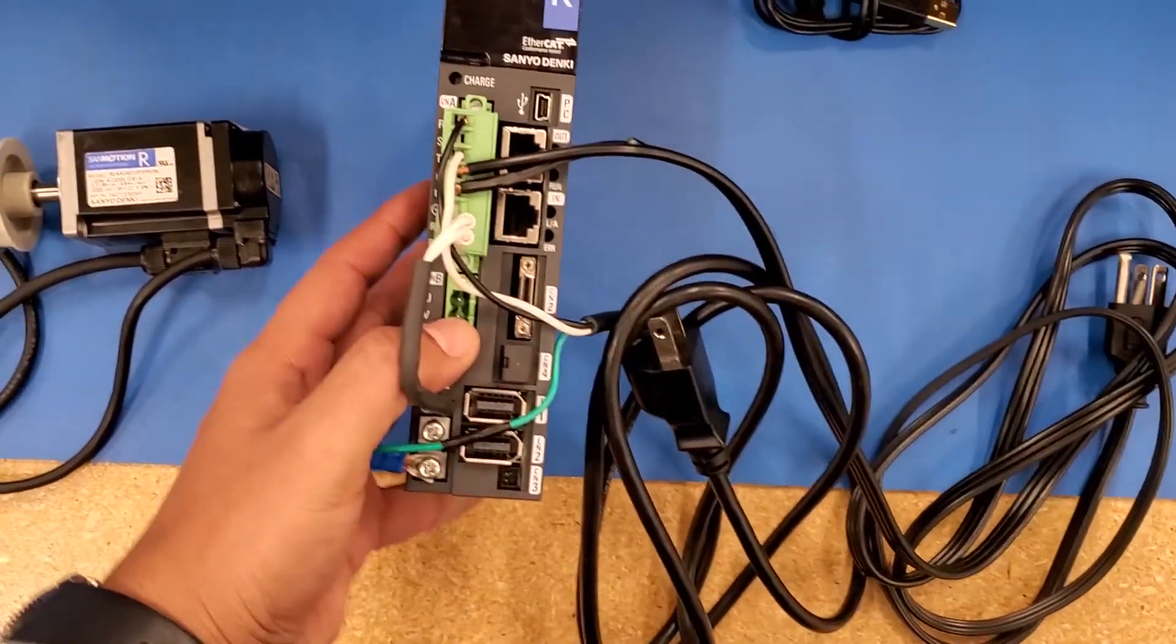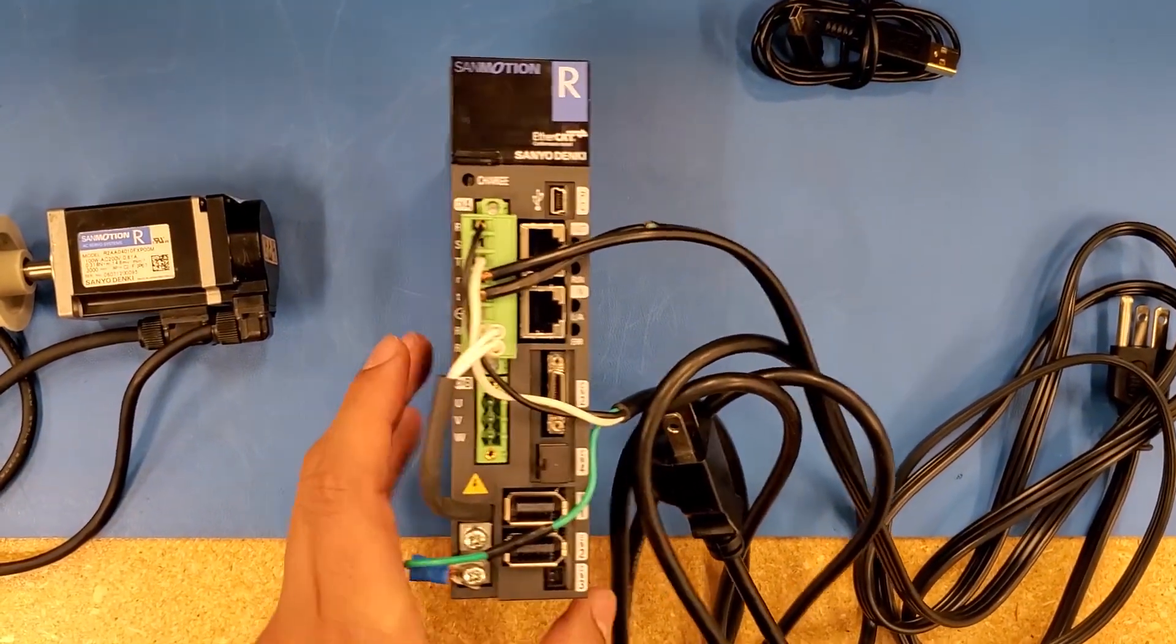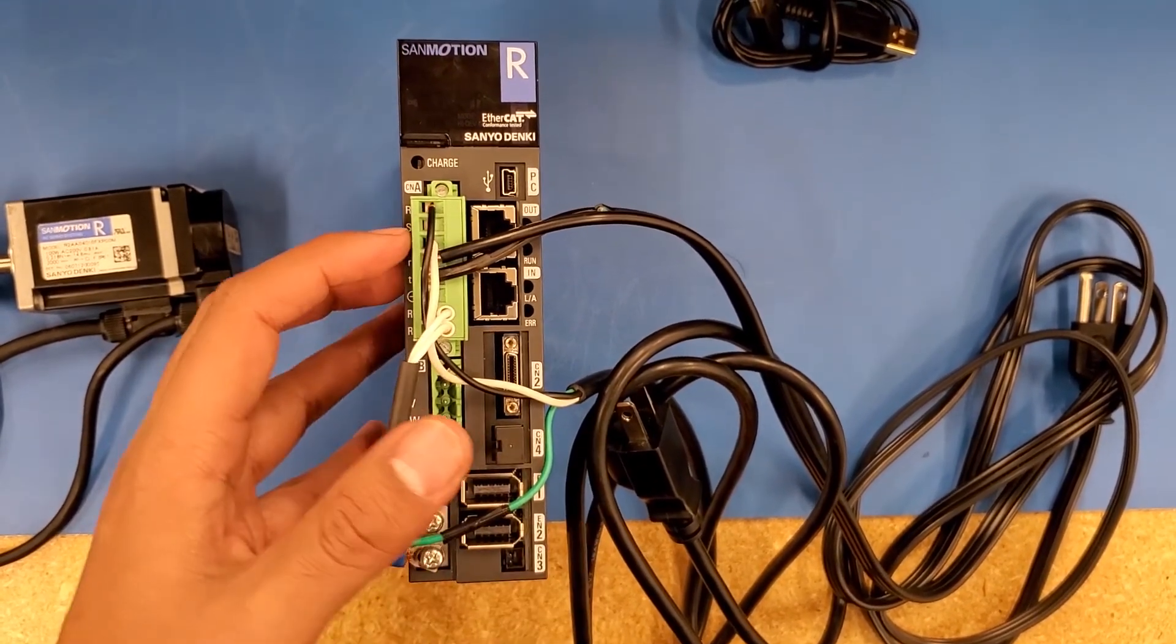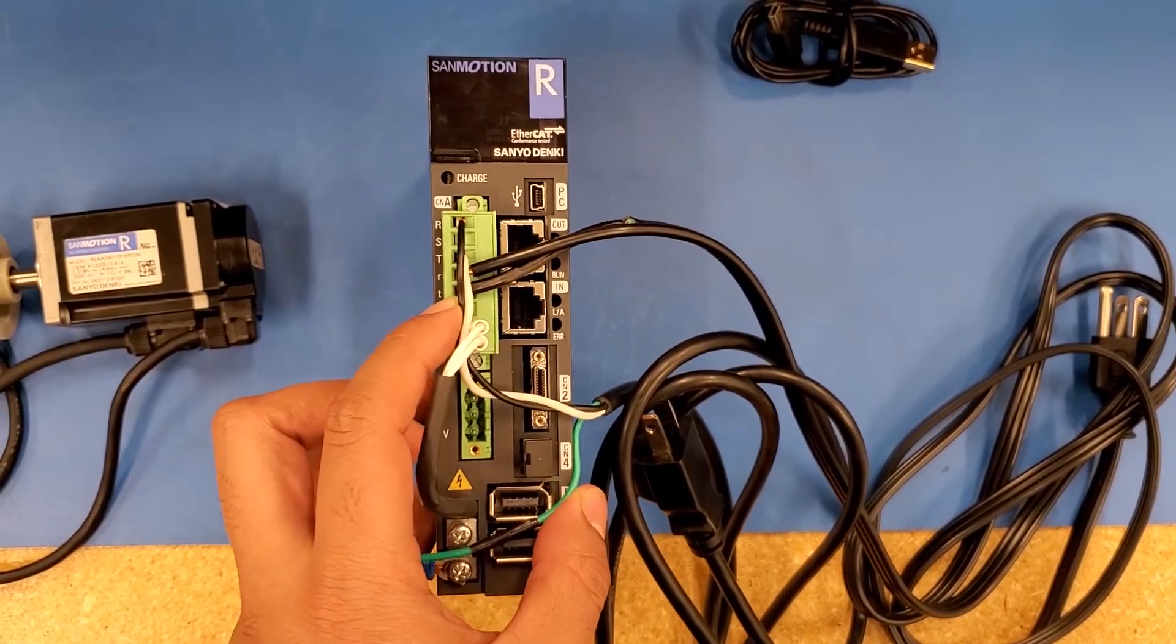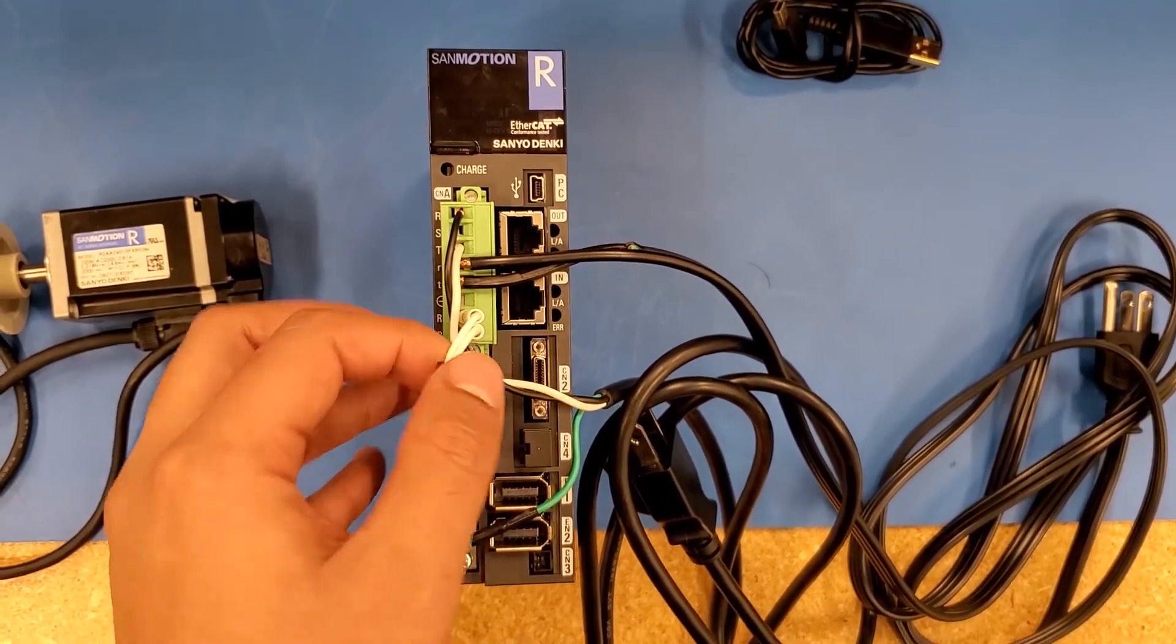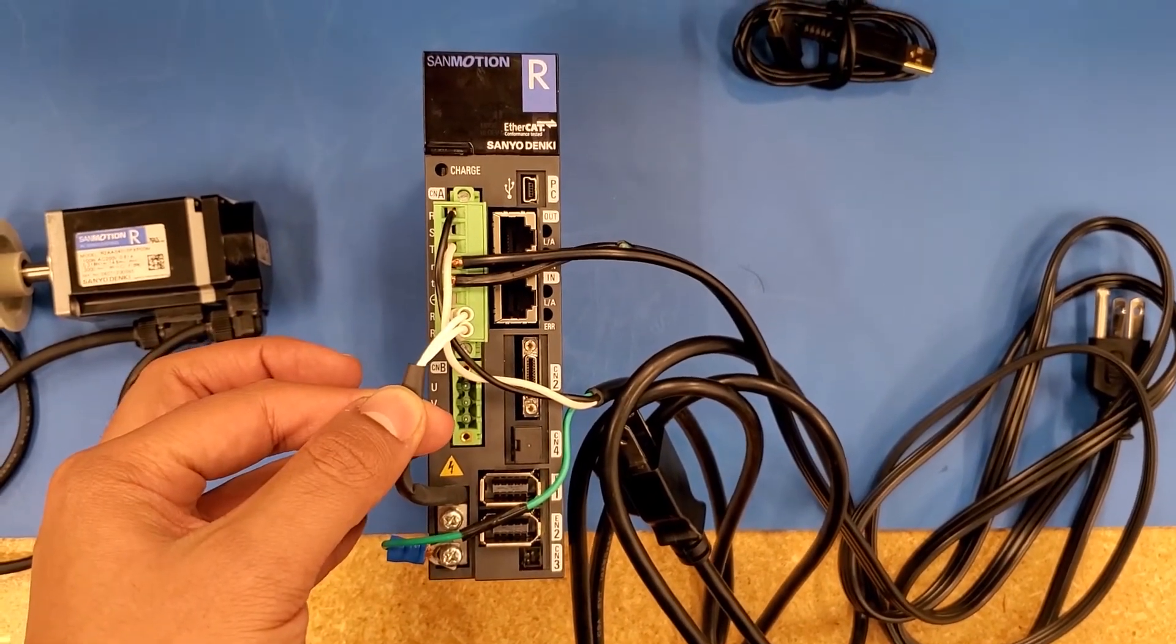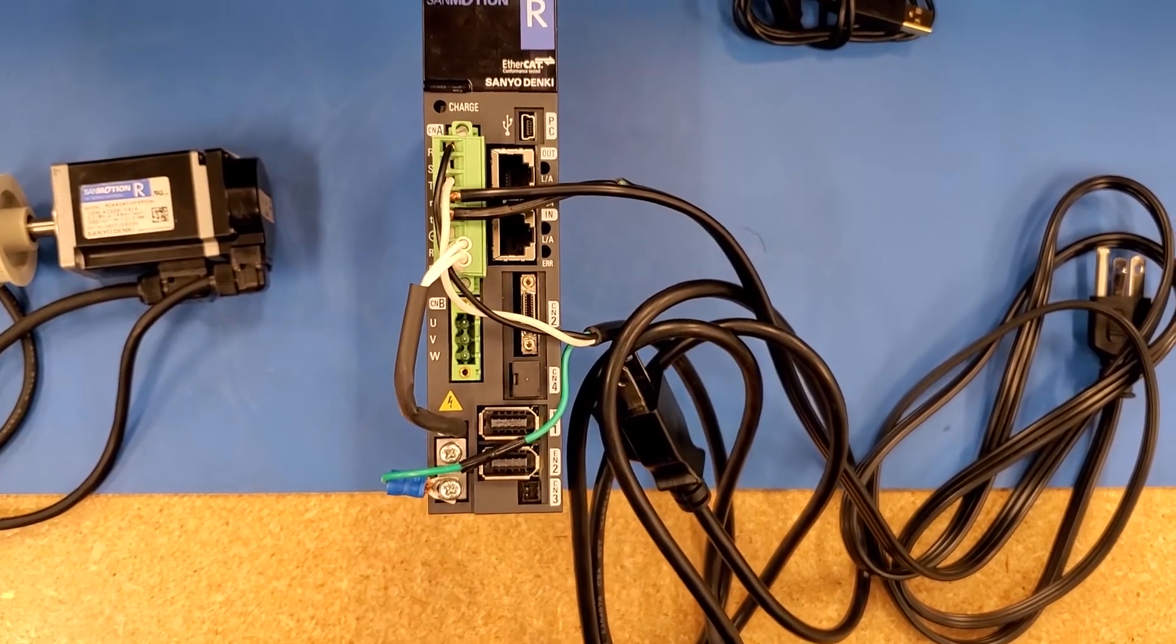This drive can be used in both single phase and three phase. RST is for three phase; I'm only using connections R and T for single phase. Small r and small t are for your control power, and your last two connections are RB1 and RB2, which is your regenerative resistor, and your ground connected to the chassis of the drive.